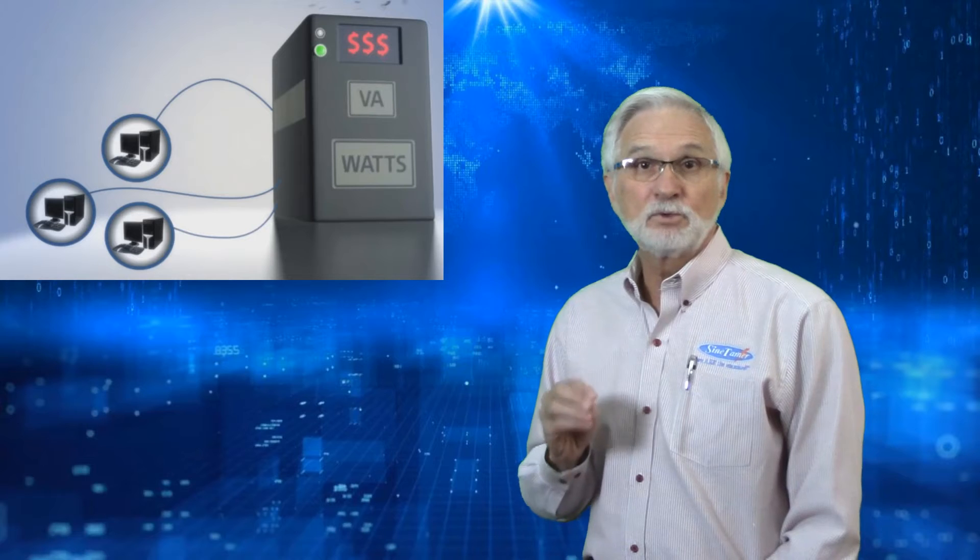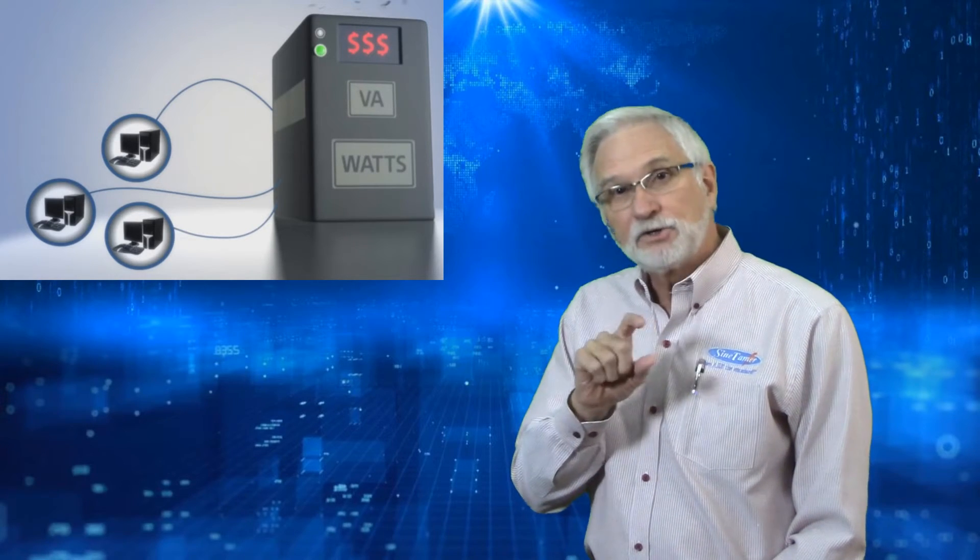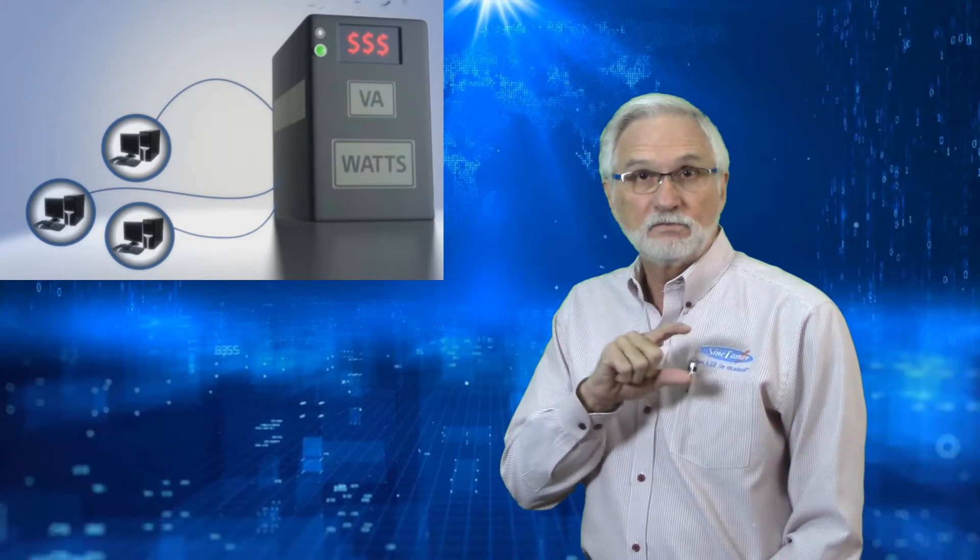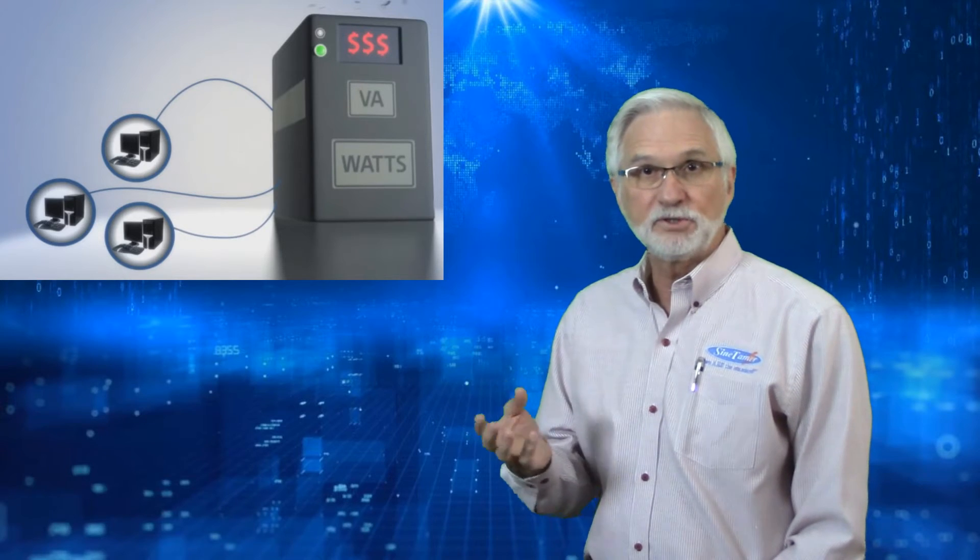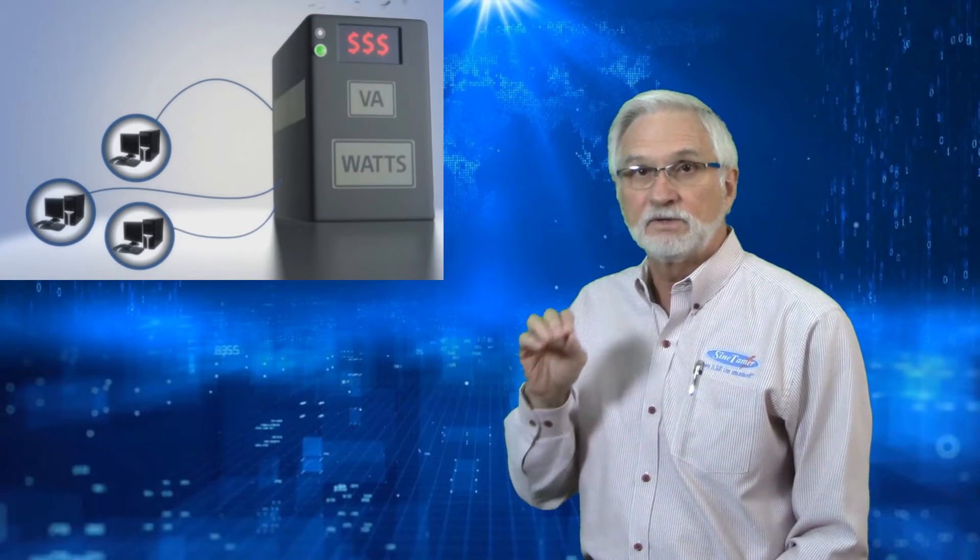Now we want to allow for a little room for growth, so we'll take that voltage, and on the back panel you can see how many watts or volt amps that the device consumes. We'll take that number times 1.2, and that gives you the starting point of how many volt amps or how many watts that we're going to be looking at.